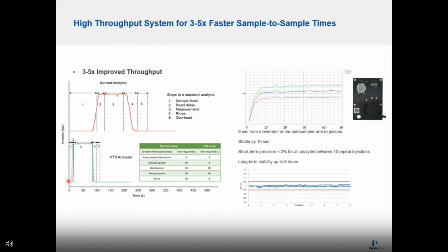we could potentially cut the exposure time to as short as 2 minutes, with the same length of time needed for analysis by ICP-MS. If you look at the signal chart on the top right, the sample is drawn up quickly by means of a vacuum into the plasma in as short as 9 seconds. From the point the probe moves into the sample, the signal is stable in the plasma much faster, and potentially we could start the ICP-MS analysis after about 12 seconds from probe down into the sample vial.